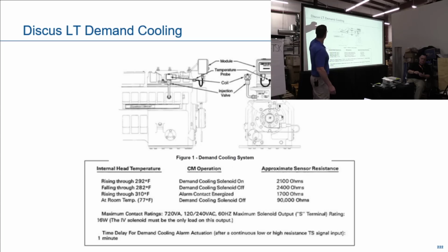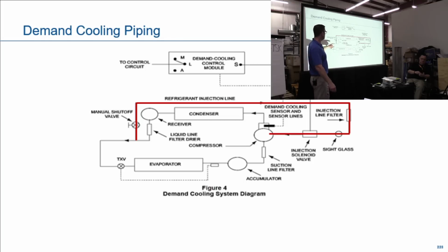Here's some of the Discus cooling. I'm not going to go through this. Check out the AE Bulletin, okay, to see the resistance of the ohms, as well as the piping for it. So you're taking a manual shutoff from your, what's this? What line is this? This is my condenser. Out of my condenser is what? Liquid line. So I got liquid coming back. It's flashed into the compressor. We're not throwing liquid in there. It's flashing refrigerant into the compressor to cool it down.